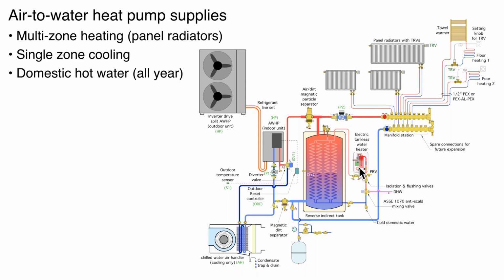I'm showing an electric tankless water heater as a booster, simply because if you're controlling this tank temperature on outdoor reset in the winter, the tank might be at 85 or 90 degrees on a mild day, and that's not warm enough to fully heat the domestic hot water. So we need some kind of a booster. It could also be a small, like a 30-gallon, tank type heater. And we've got a variable speed pressure regulated circulator, and then again, a manifold with home run circuits going out to whatever: panel rads, towel warmers, floor heating circuits. All of these can be controlled based on thermostatic valves. So it's a nice combination: space heating, space cooling, and domestic hot water.